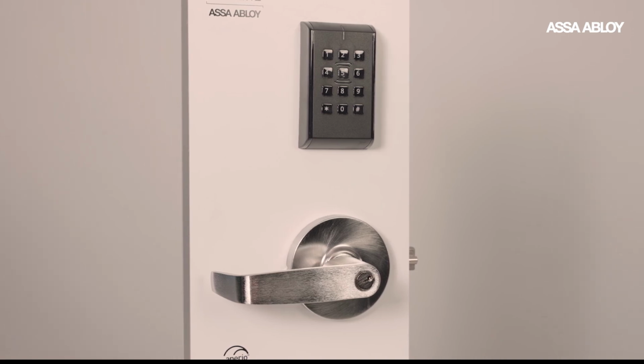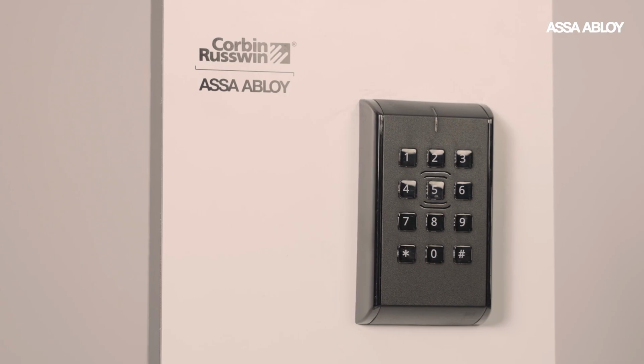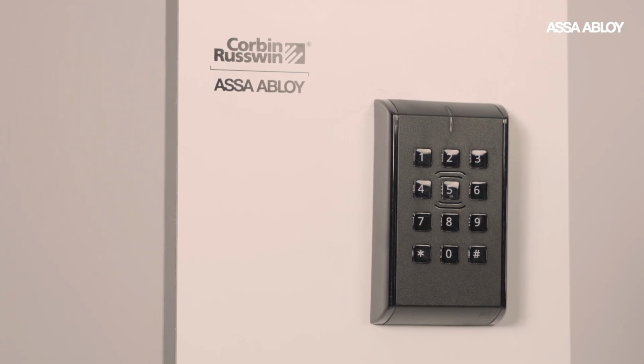You actually get the Aperio lock, which is a wireless lock that communicates to a hub, and you're able to communicate in real time. We also have the option for our Wi-Fi enable lock, which connects to the infrastructure that is existing in the facility. You mentioned the Aperio wireless solution as well as the Wi-Fi solution. What's the difference in the infrastructure required for those? Our Aperio product connects back to the EAC controller. Our Wi-Fi enable product connects to the 802.11, which is the existing Wi-Fi network in the facility.